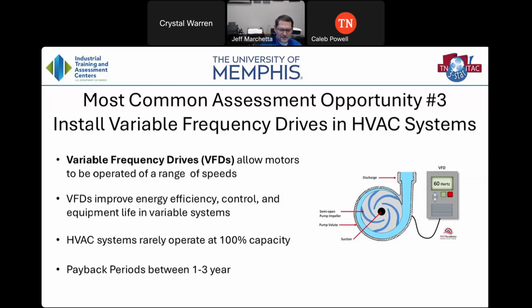So payback periods for VFDs typically fall in the 1 to 3 year time frame, okay, which is why they're good. Now you see in that picture there, you'll see that little VFD drive. It says 60 hertz. That's just telling you it's a VFD drive. One thing I'll say is if you have a VFD drive installed and it always says 60 hertz, that's not a good thing because it means it's not varying and you're not getting any benefit out of the drive.